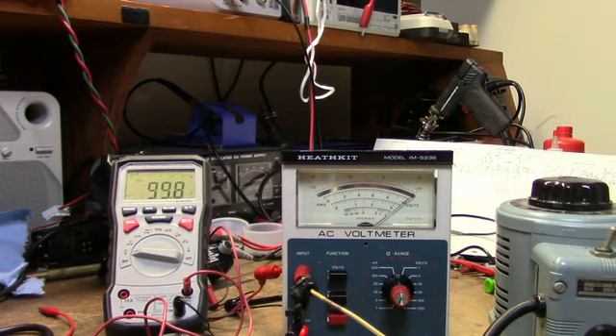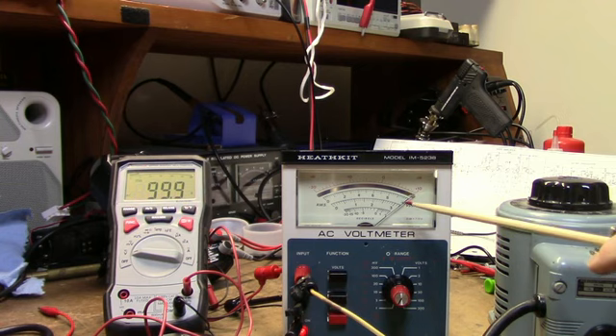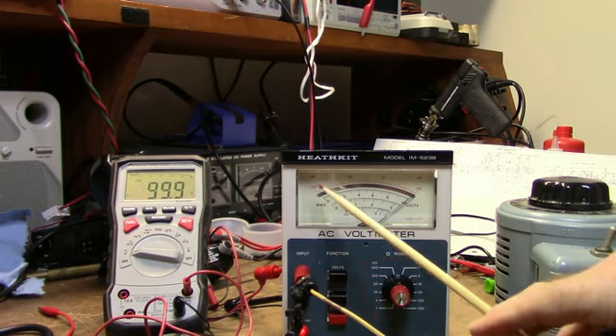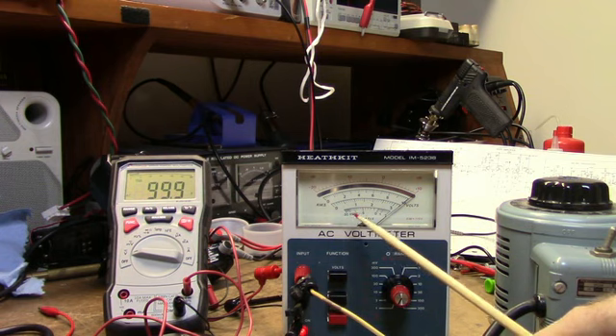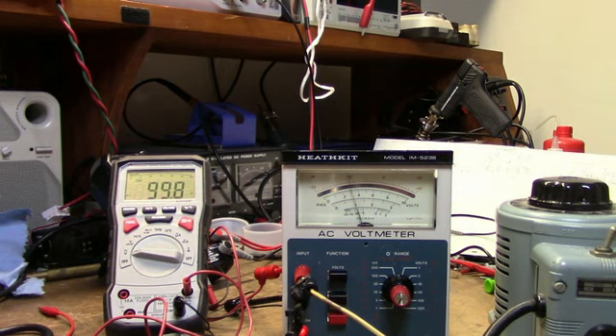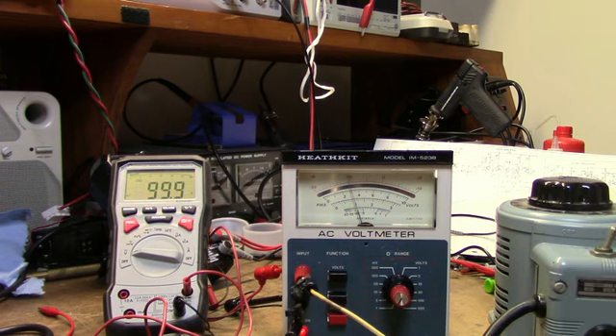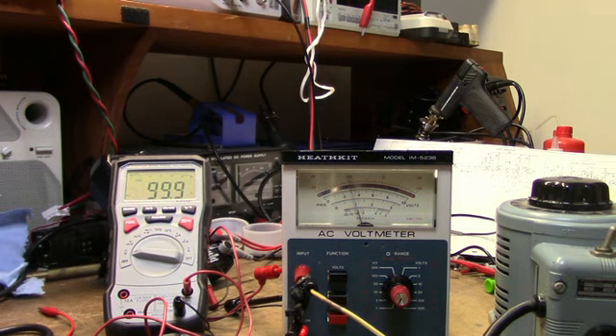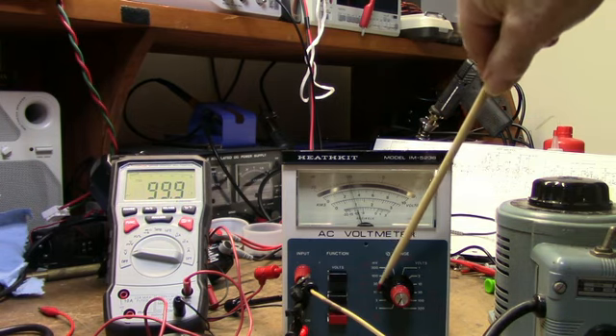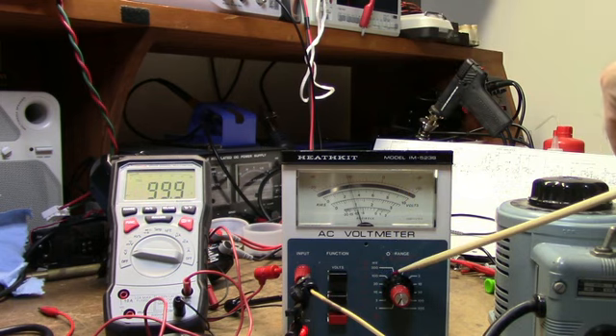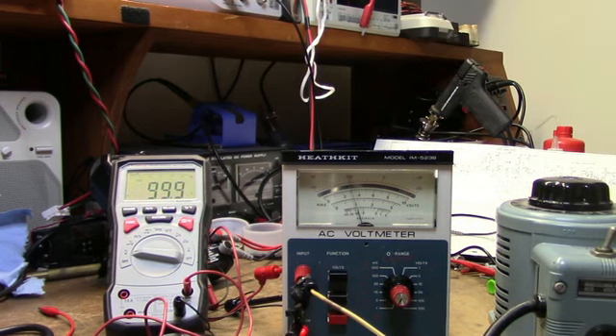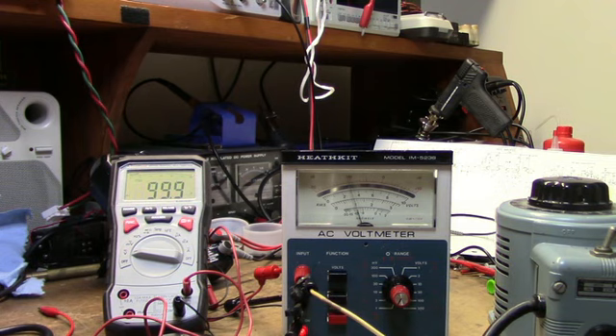There's about 30, measuring a little bit high. Go up to the 100 volt range. Let's stop at 60. We're measuring 60 or 61 on the DVM, and on the 100 volt range we're right at 60. Let's go up to 100. There's 100, and that's pretty much on 100 volts. On the 300 volt scale, it's right on the 1. It looks like we're accurate.